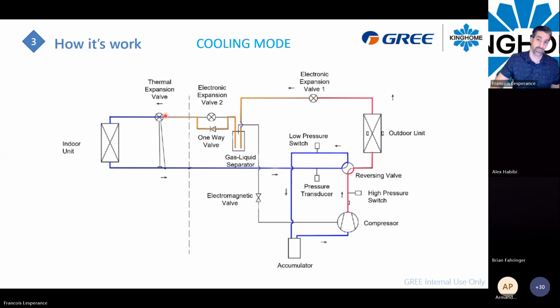On the A-coil, we will have a thermal expansion valve. At this point, this metering device will reduce the pressure. So we go from high pressure liquid refrigerant here to low pressure refrigerant on the other side of that valve. Then we will hit the indoor coil, and we will gain BTU inside of it.